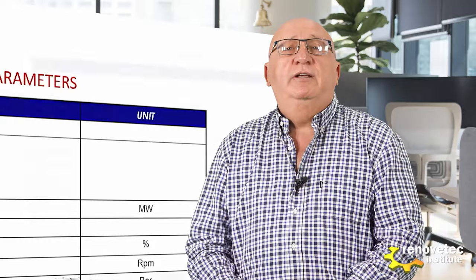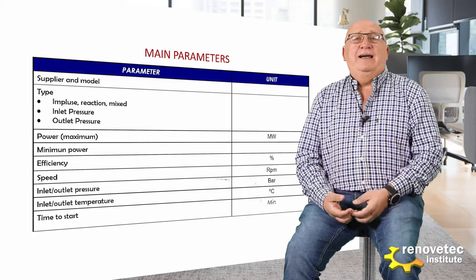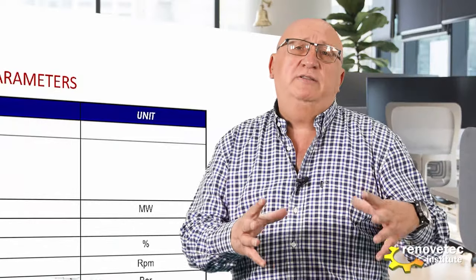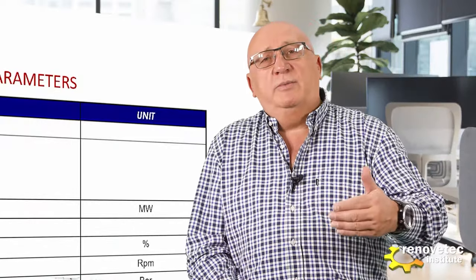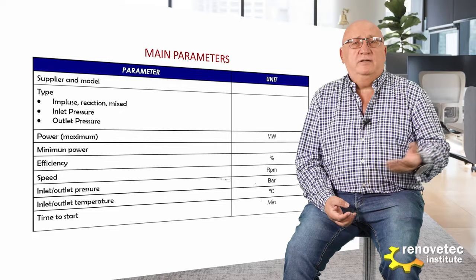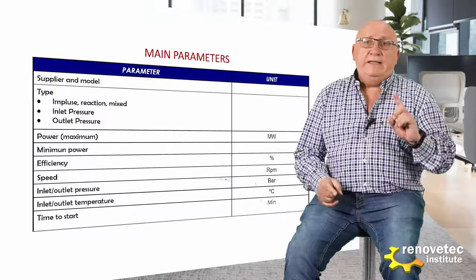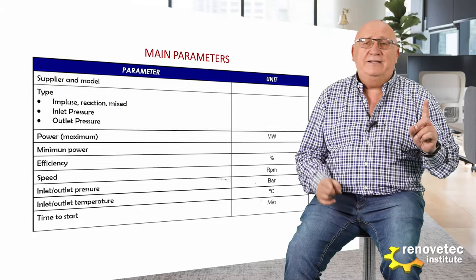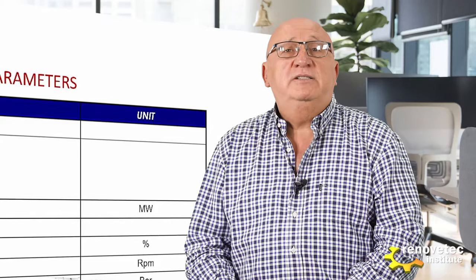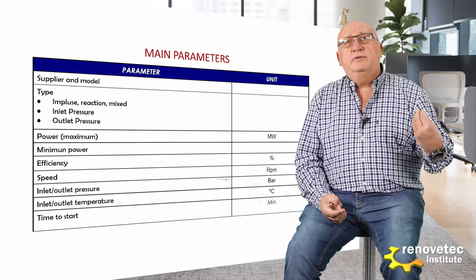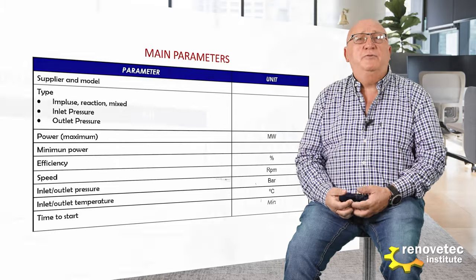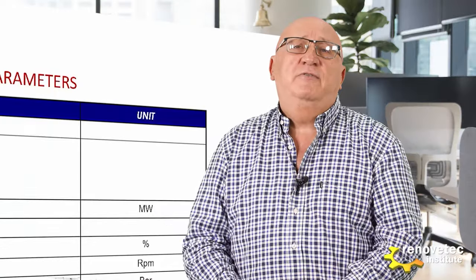The speed of rotation is another very important characteristic. Normally the most common situation is that the turbine rotates at the same frequency as the grid. But in small turbines this is not normal, and the turbine normally rotates at a higher speed than the frequency of the electrical energy. Inlet and outlet temperature and inlet and outlet pressure are two more very important characteristics. And the last one is the time to start — the time that the process of accelerating the turbine, synchronizing, and reaching full power takes. This is a very important characteristic.